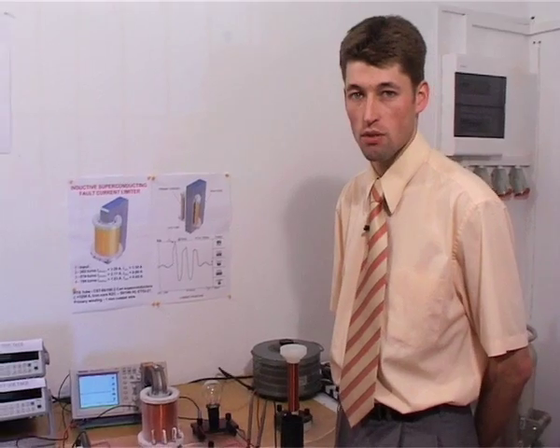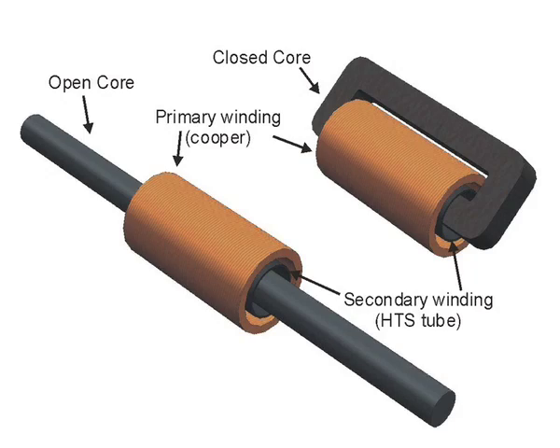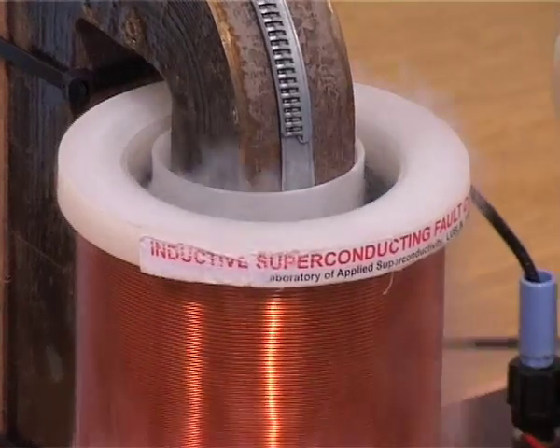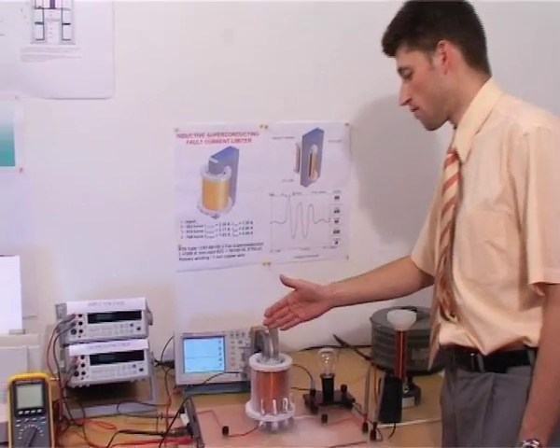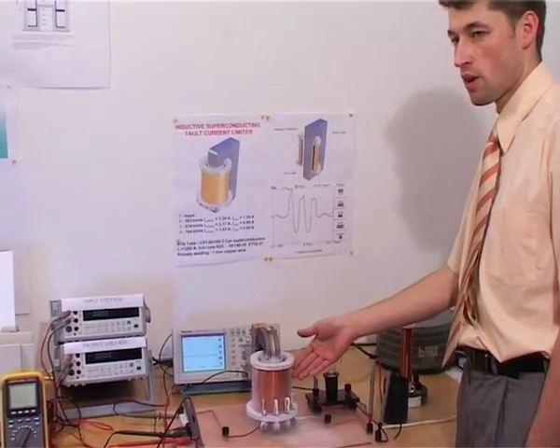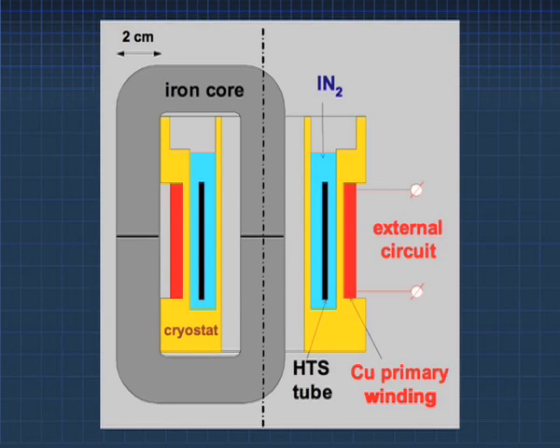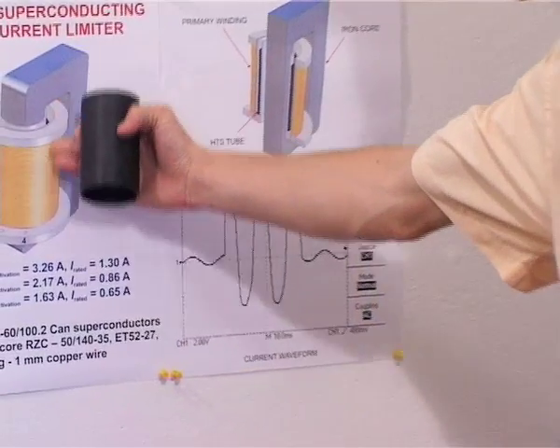Inductive superconducting fault current limiters do not need current leads to the superconducting element, and they are simpler in structure than the resistive ones. There are two types of superconducting fault current limiters: one with a closed core, and another with an open core. The inductive superconducting fault current limiter with a closed core consists of an iron core and a copper primary winding. Inside the limiter is a ceramic superconducting tube which acts as a secondary winding.